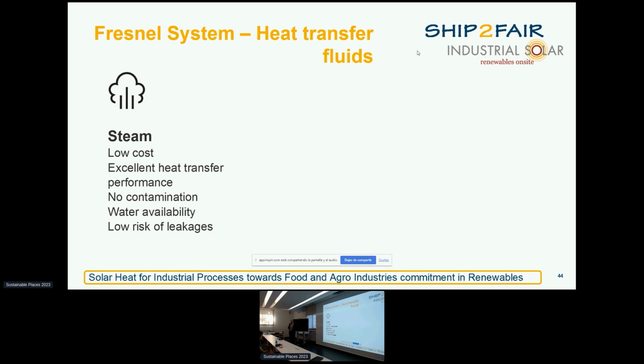So what are the heat transfer fluids that we work with? I'm showing three options here because I think this is always a good question, what to do with this type of collector, this technology. Steam for the industry, I think, is the preferred option, normally speaking. In some cases they also use a hot water grid, but normally they prefer the steam system because steam is easy to transport. We have small pipes. And as we don't interfere in their operation, we normally try to integrate at the same level that they supply. The advantages of steam are the low cost, the heat transfer capacity, the performance, no contamination, and water availability, and the risk of leakage is actually very minimal.